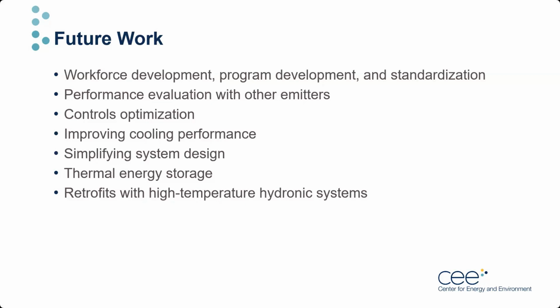And finally, retrofits with high-temperature hydronic systems. This would include high-temperature emitters like high-mass radiators that may see inadequate heat delivery when used with lower supply temperature systems. Further research into retrofitting these systems to homes with existing high-temperature distribution will help us understand these limitations and the necessary additional design work required to remedy this issue.